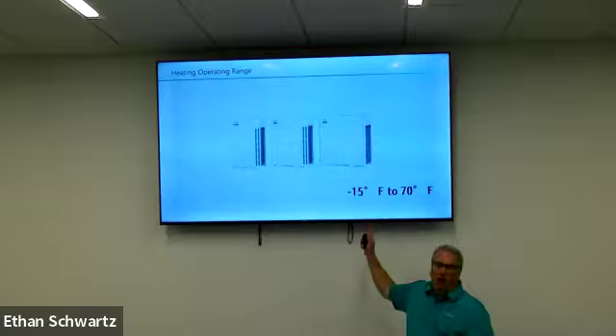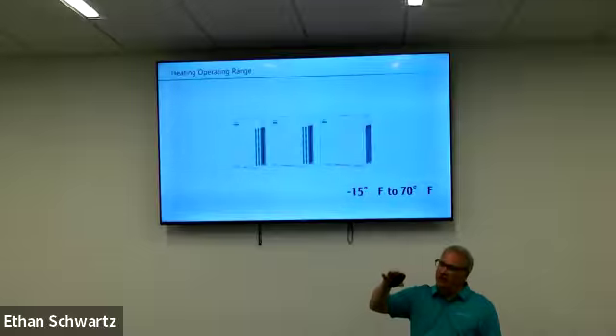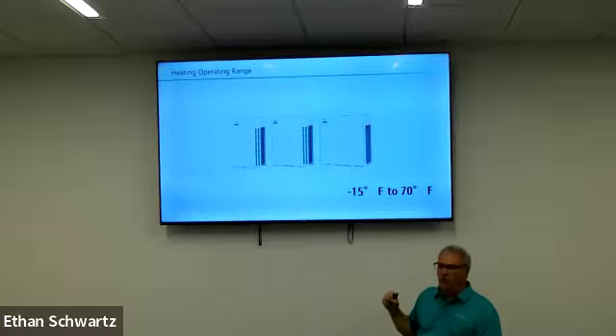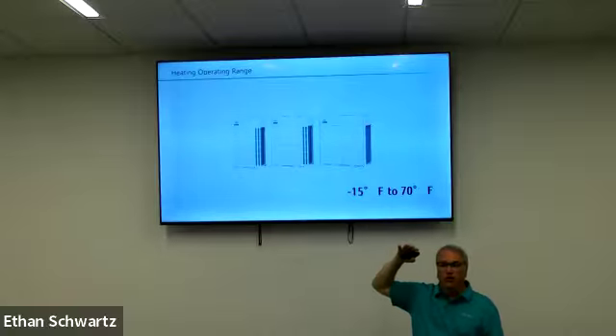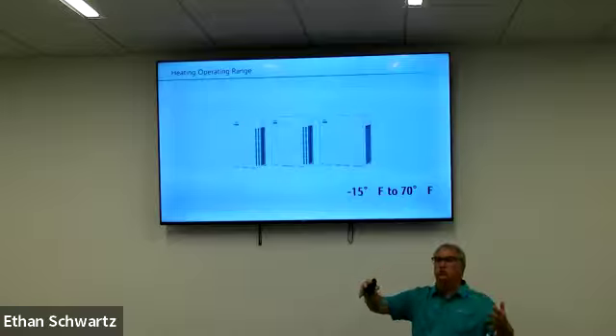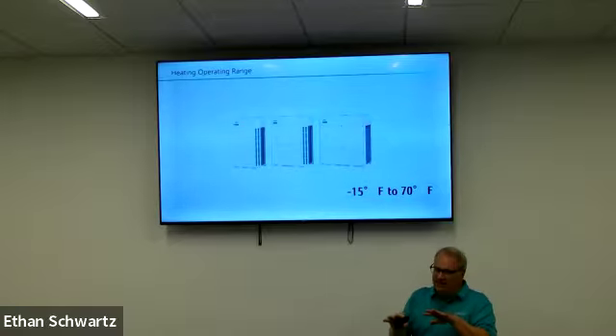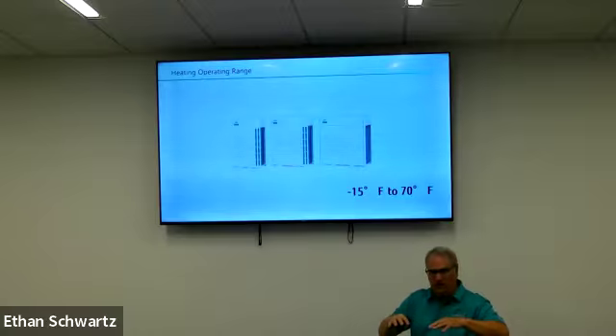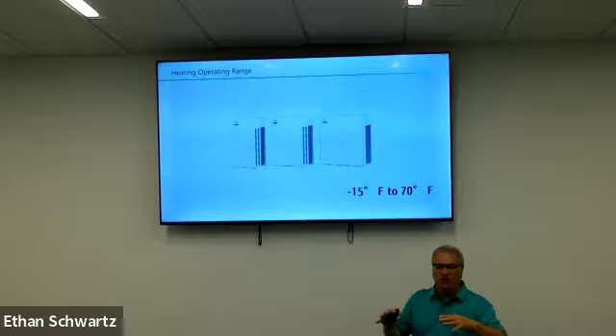is when you get below about -7, -8 on a heat pump product, the defrost cycle, which all heat pumps are going to have, the defrost cycle is going to do what? Melt the frost, and that gives us what? Condensate. At 7 to 8 degrees below 0 Fahrenheit, that will create enough condensate, and it will take enough time to get out of the pan, that it probably is going to start to freeze. And if you have that extended over time, now you're going to build up ice. When you build up ice, what does ice do when it freezes? It expands, and you can crush the bottom of that coil.